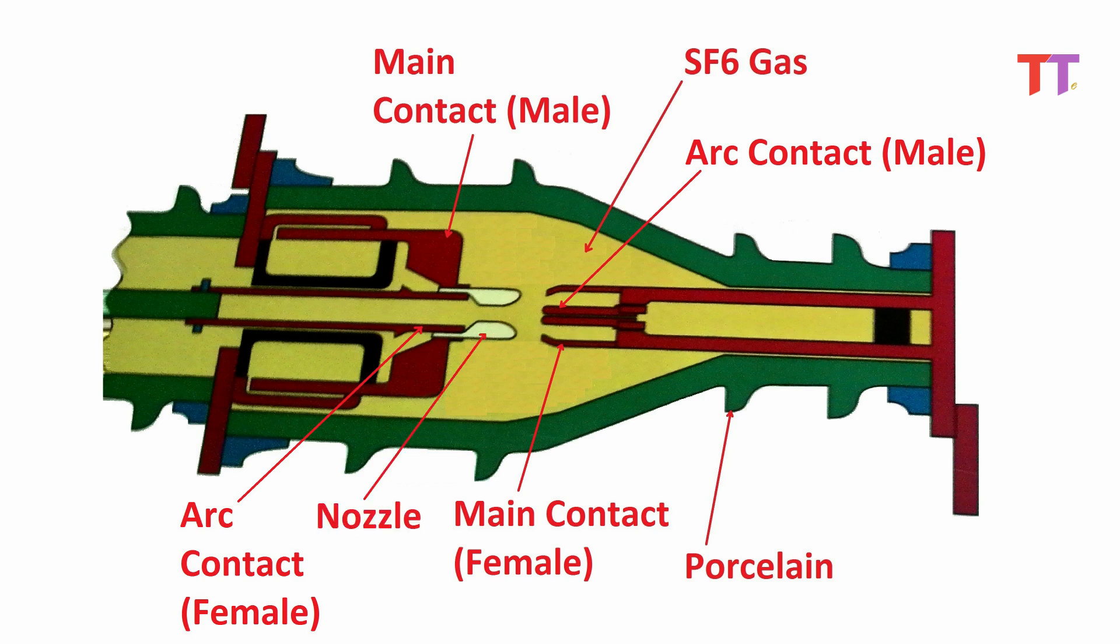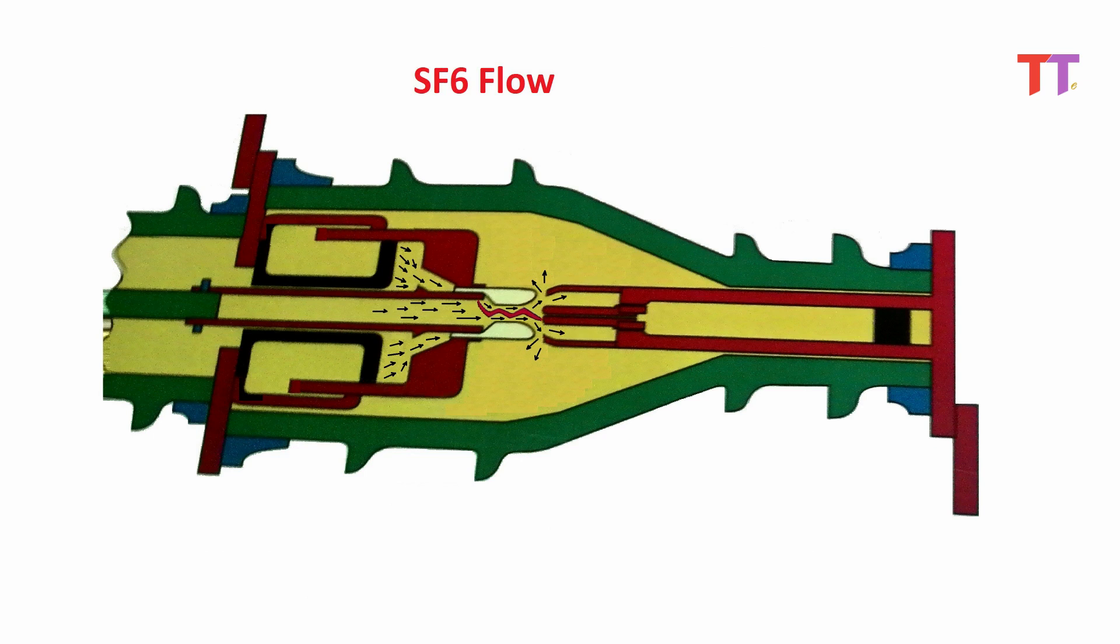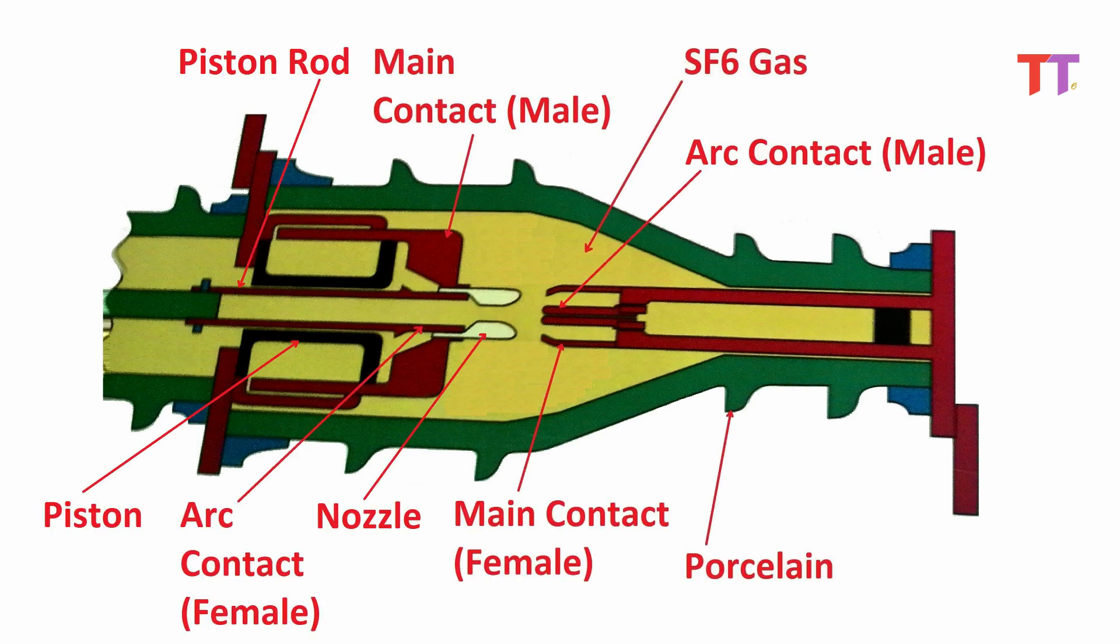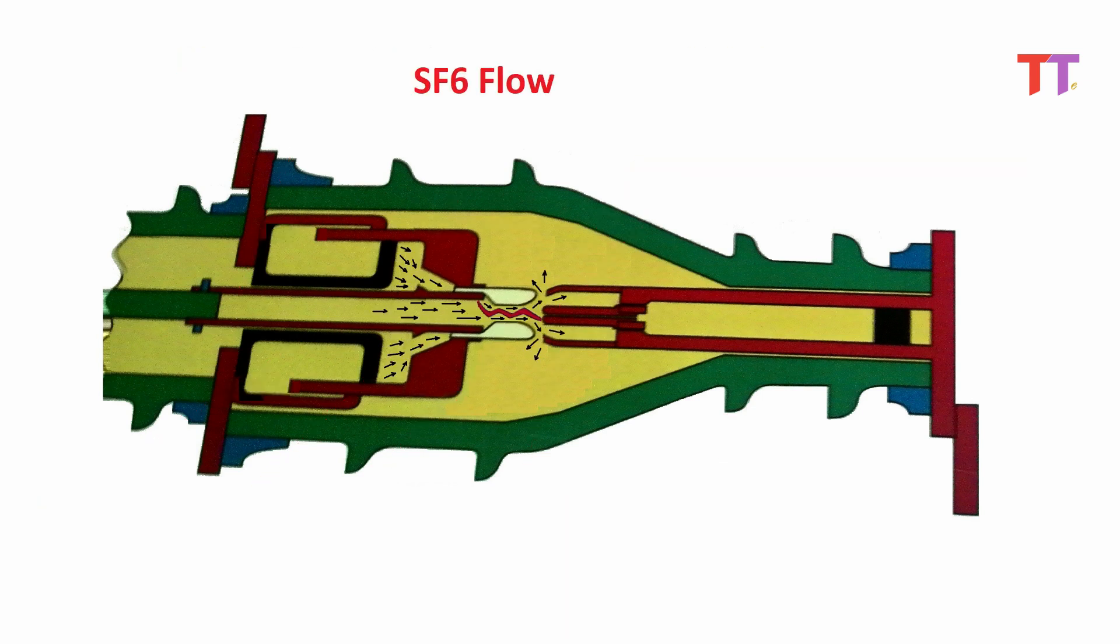This is nozzle which is made of non-metallic insulating material. Function of the nozzle is to direct SF6 flow towards arcing region to accelerate arc quenching. These are pistons and this is piston rod. Pistons are used to push SF6 to blow it on arc for effective arc quenching.